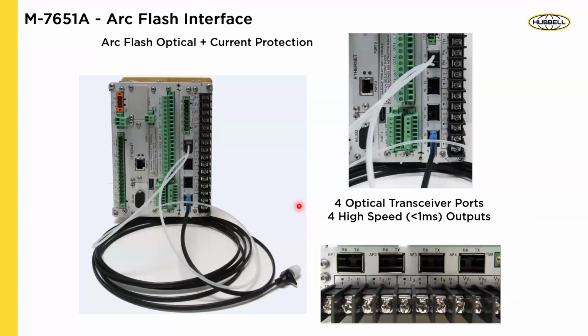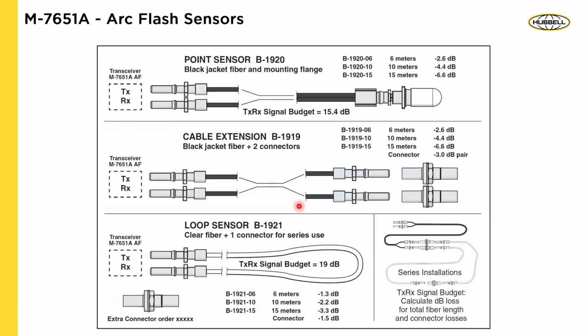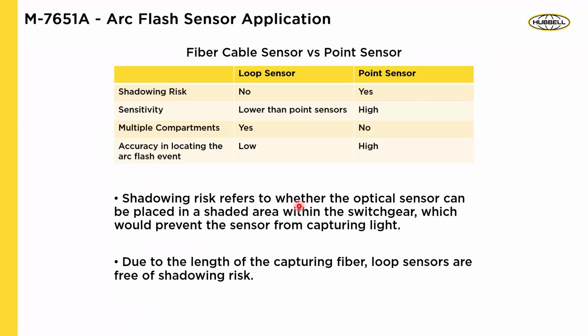Just some more pictures for that. And then the high-speed outputs are obviously solid-state relays, so then you have less than 1 millisecond of output. The whole purpose for the speed is to limit the incident energy, right, on the arc flash. So there's some more information. You could find all of this information in our data sheet when you're ordering arc flash to see what the part numbers are, what the length could be, the attenuation, and all kinds of details, how to calibrate and how to set.